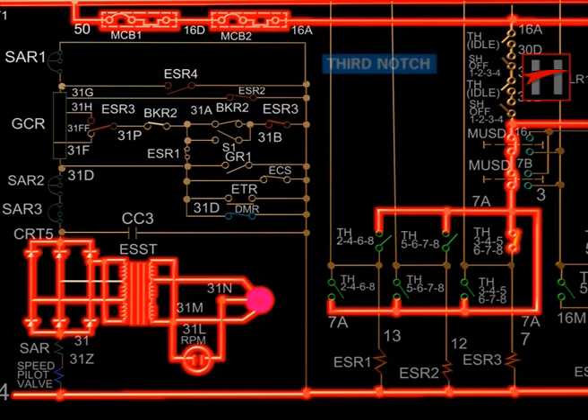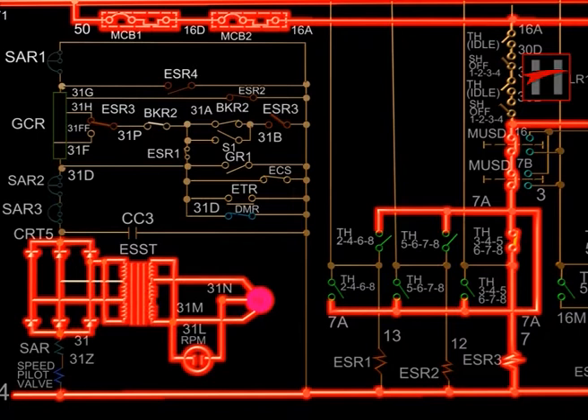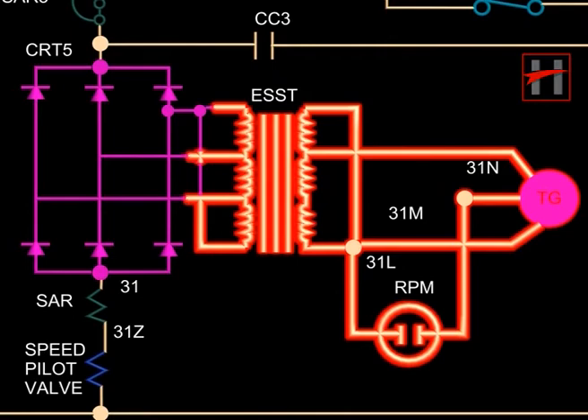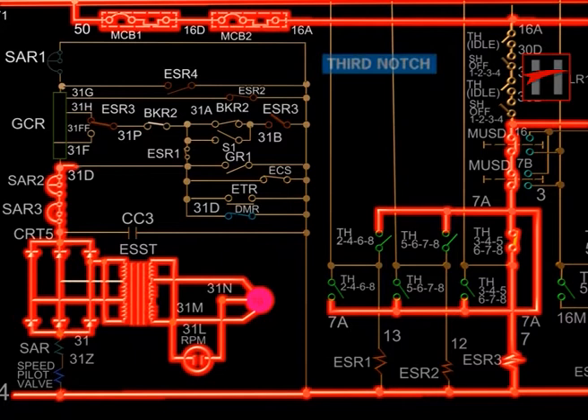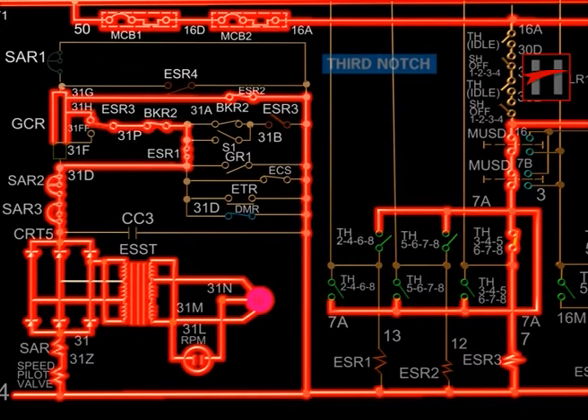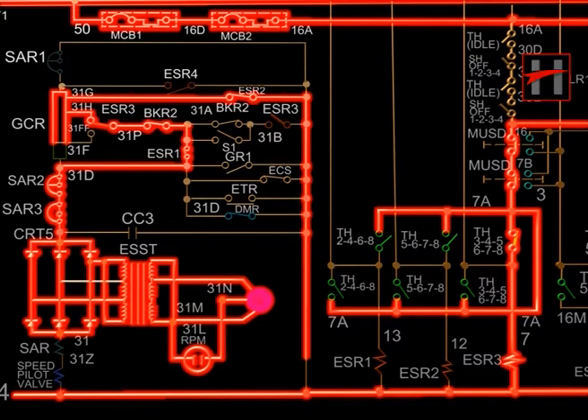In the third notch position, ESR-3 gets energized. The normally closed interlock of ESR-1 closes due to de-energization of the ESR-1 coil. The interlock of ESR-3 changes position from 31F to 31FF. The rectified output of the tacho generator flows through CRT-5, SAR-3, SAR-2, cable 31D, interlock of ESR-1, BKR-2, ESR-3, cable number 31FF, GCR, interlock of ESR-2, and completes its circuit with cable number 4, speed coil of pilot valve, cable number 31Z, SAR coil, and cable number 31.